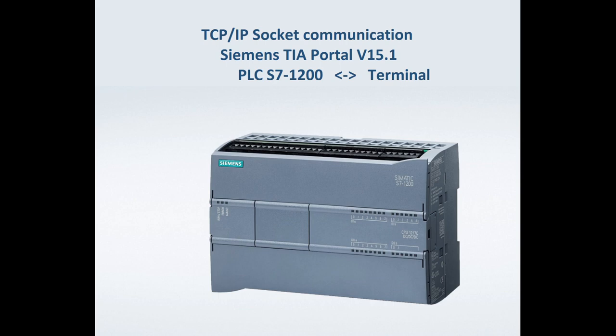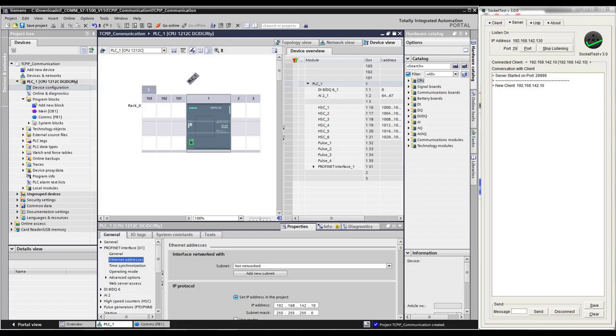TCP/IP is using standard Ethernet hardware, like switch, cables etc., so you can use existing Profinet network hardware. It's master-slave asynchronous communication, so one device has to be master. In other terminology it's called client, which is a little bit confusing. Other one is slave, also called server. Master is responsible for initiating communication, based on IP address and port number. Slave is just waiting for incoming communication on given port, then it can respond to master.